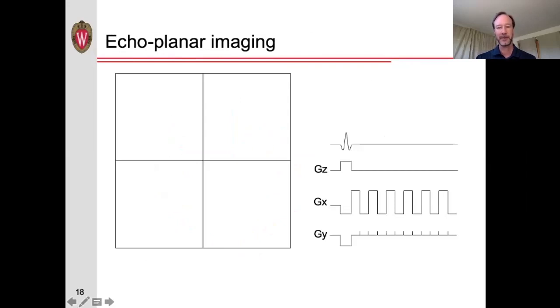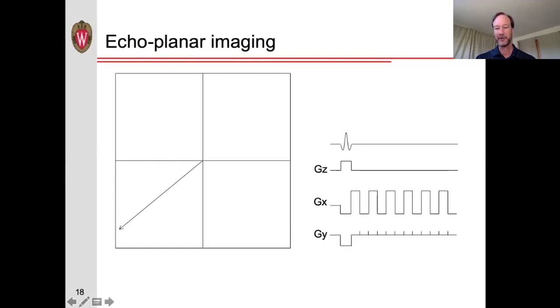Another technique used quite commonly for functional MRI and diffusion tensor imaging is echo-planar imaging (EPI). After exciting the spins and placing us in the center of k-space, we apply gradients in the negative X and Y directions, moving us to the negative corner of k-space. We then start acquiring data, applying a positive lobe in the X direction to move right, then a small blip in the Y direction to step slightly further. We then reverse the X gradient and scan back, repeating this backwards and forward scan.